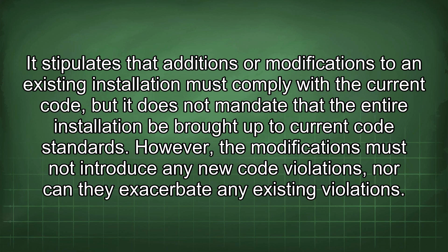Both New Jersey's Rehab Code and Massachusetts Rule 3 permit modifications to existing electrical installations that do not meet current code standards without requiring a complete system upgrade. New Jersey's Rehab Code is detailed in the New Jersey Administrative Code at NJAC 5:23-2.20. It stipulates that additions or modifications to an existing installation must comply with the current code, but it does not mandate that the entire installation be brought up to current code standards. However, the modifications must not introduce any new code violations, nor can they exacerbate any existing violations.